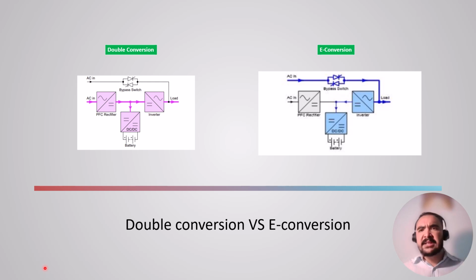Now, how does this work? The UPS will be on bypass. It will take only 10% of the load to push the inner components inside the UPS, like the rectifier and inverter, to create stress. From the stress, it generates heat, and from this heat it moves in a loop, testing its status under different loads.